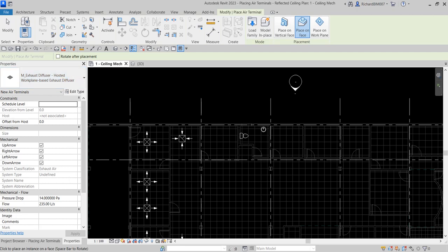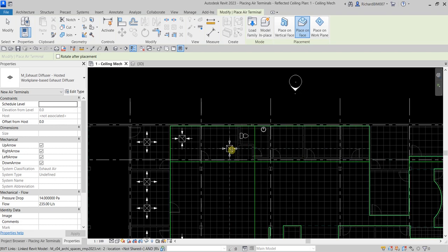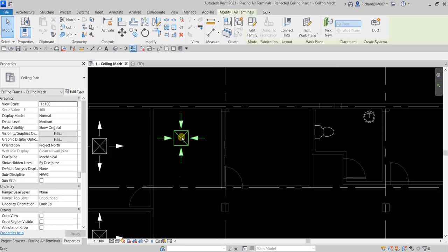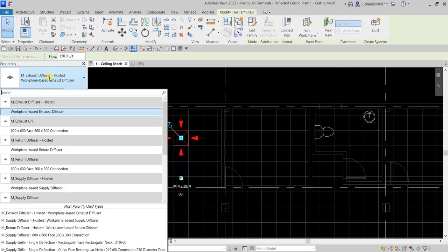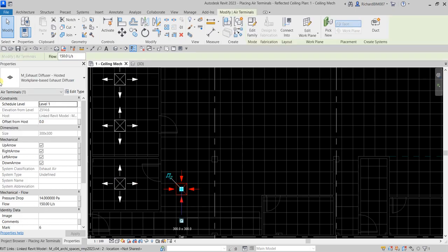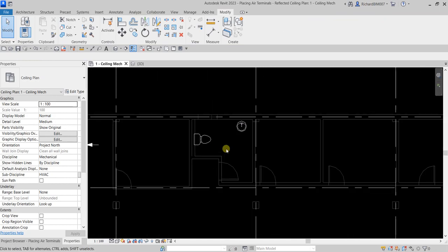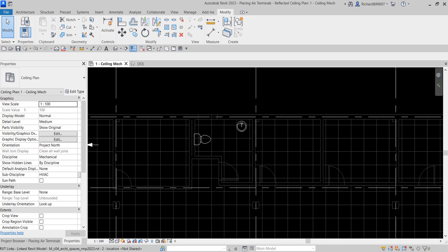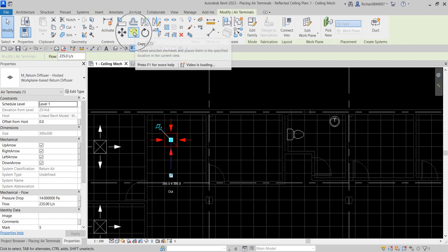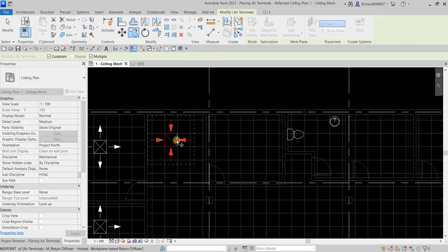Actually, those last two placed should be return diffusers, not exhaust. Select Modify, click the terminal, and change the type to Return Diffuser. Do the same for the other one. For the exhaust placement, you can copy an existing air terminal and then just change its type, rather than using the air terminal tool from scratch.